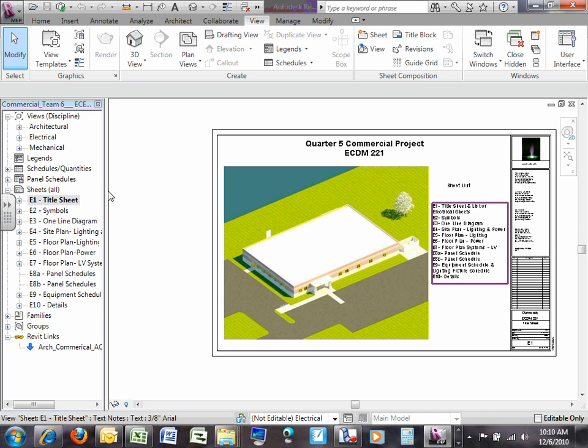Where do you get this information from? Our friends, the mechanical engineers. Where do they have it? They give you cut sheets at the end. You're going to see all these have cut sheets at the end. I see a cut sheet, you guys read through it, and it refers you back to the cut sheets that talk about it. Air handling unit, for example, go to the cut sheets: it's a 15 horsepower motor, 208 volts.